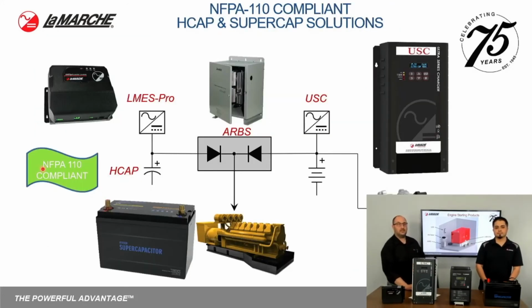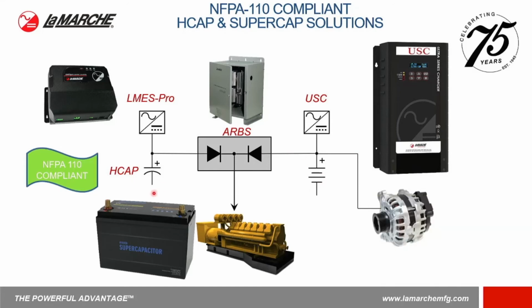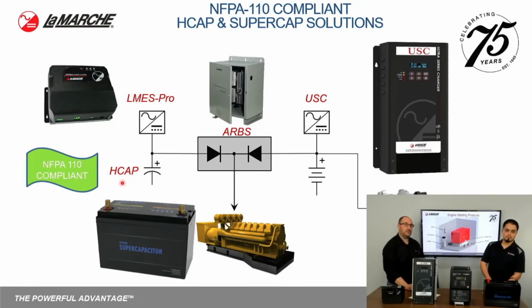Taking a look at a system that must be NFPA 110 compliant, technically in the NFPA 110 as written in 2019, they didn't have the vision of having an HCAP in the system. The only energy storage devices that would be allowed would be a lead acid or a NiCad battery. We've been able to utilize HCAP or even EDLCs in the past through an ARBS in a system like this. In addition to participating in the EGSA and in the IEEE, we'll also be participating in the NFPA 110 and seeing if we can encourage the inclusion of hybrid supercaps based on actual test data.